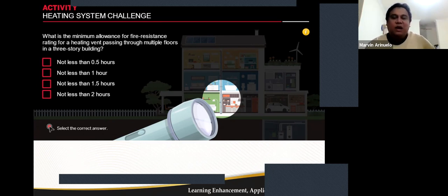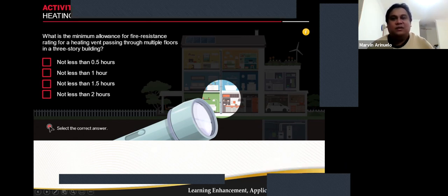What is the minimum fire resistance rating for heating vents passing through multiple floors in a three-story building? Vents passing through floors of a building require the protection of vertical openings enclosed within a wall having a fire resistance rating of no less than 1 hour. So the answer here is B. If the building is less than 4 stories, and here it is 3 stories, we consider it less than 4 stories. So no less than 1 hour is the answer.